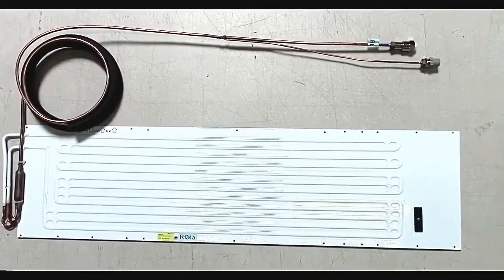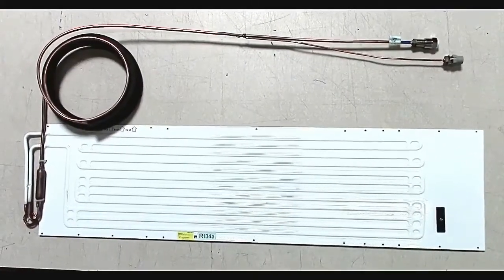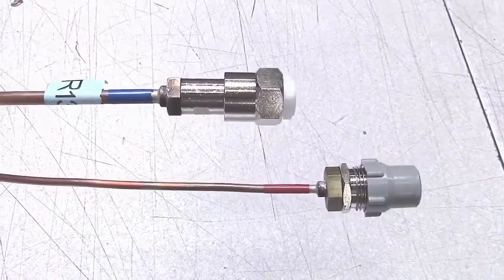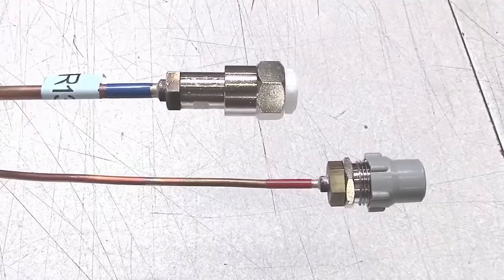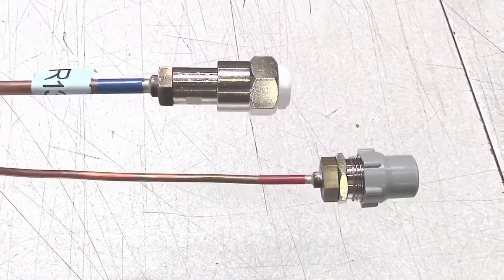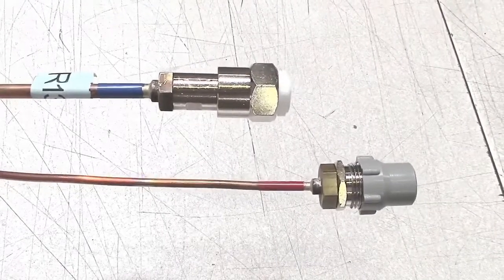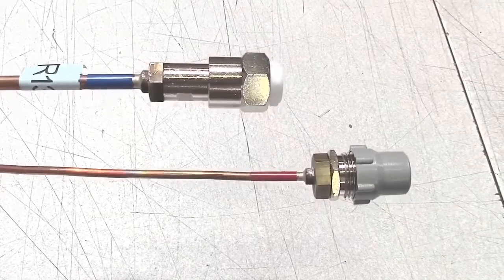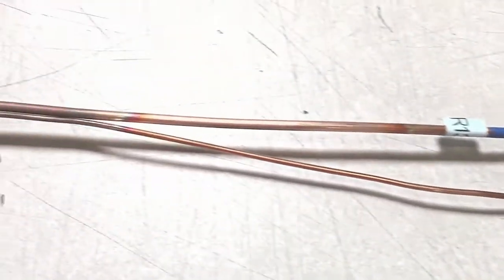Using this flat 200F evaporator from Frigoboat, we'll describe the two different types of cap tube blockages you might come across. At the end of every 10-foot line set on Frigoboat evaporators, there are two couplings attached to the tubes. The larger tube is the suction line from the evaporator back to the compressor, carrying the low pressure gas back to the compressor. The smaller of the two is the liquid line, which carries liquid under high pressure to the evaporator from the compressor condensing unit.